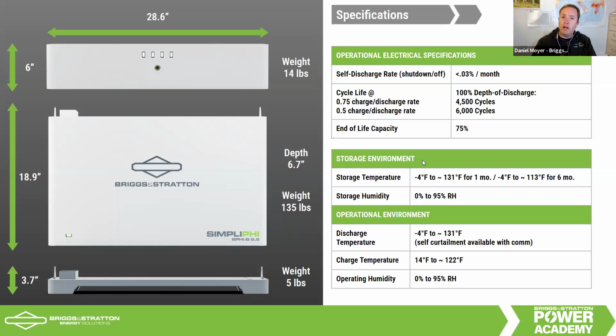Although we offer unlimited cycles, I have some projected life cycle figures here. Back in the old lead acid battery days, we were always focused on depth of discharge - don't discharge the battery below a certain rate. That's still true; 80% depth of discharge does give you a lot more life on these lithium ion LFP batteries. But it's also the charge rate, or how fast you're charging or discharging, that affects life. At 0.5C, a C/2 discharge rate, you charge the battery up in 2 hours and can discharge it in 2 hours.